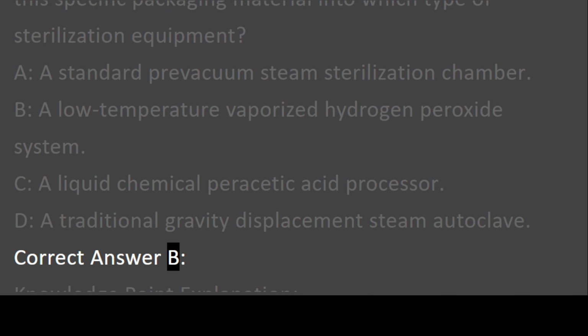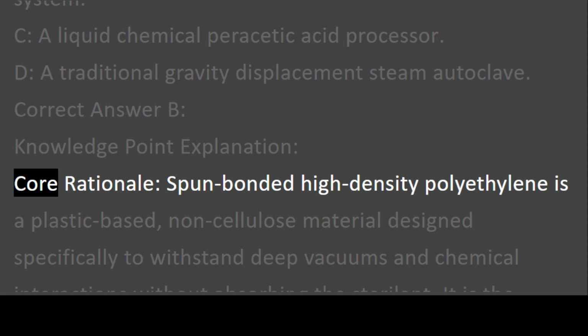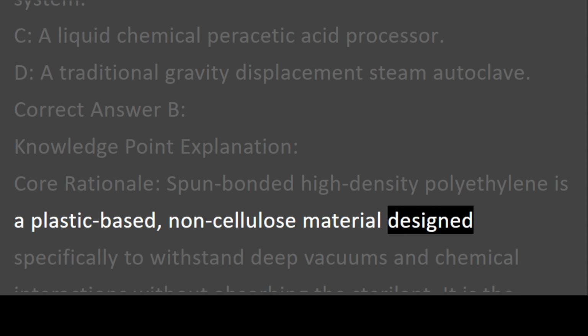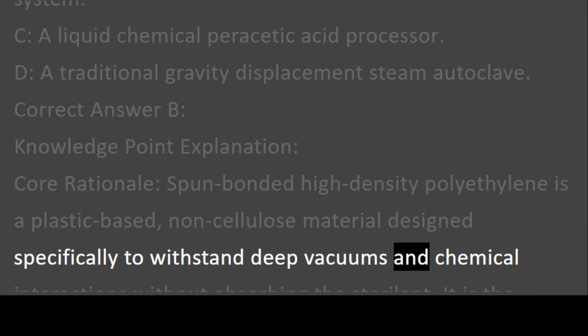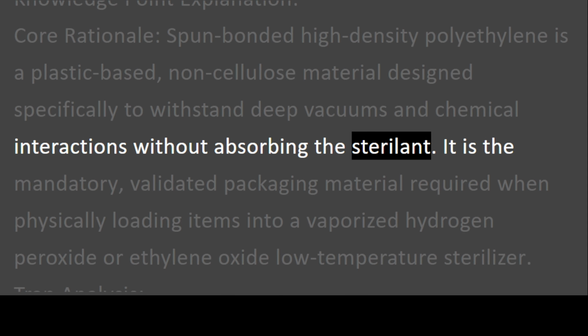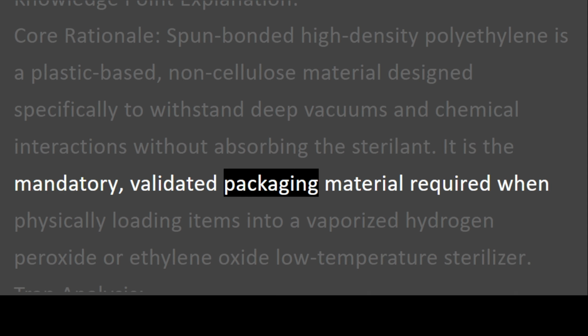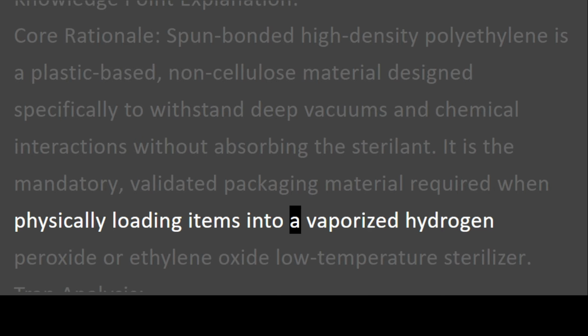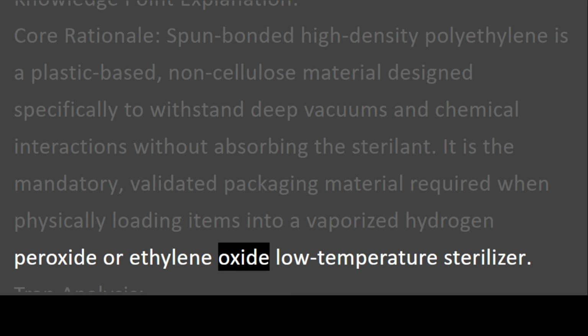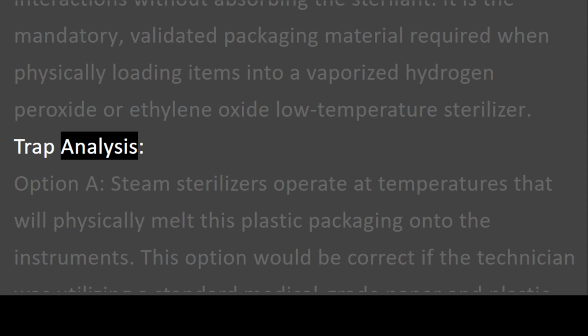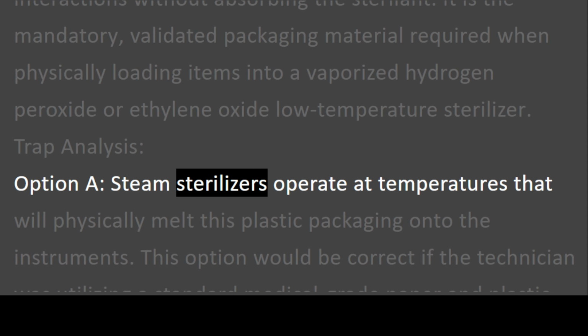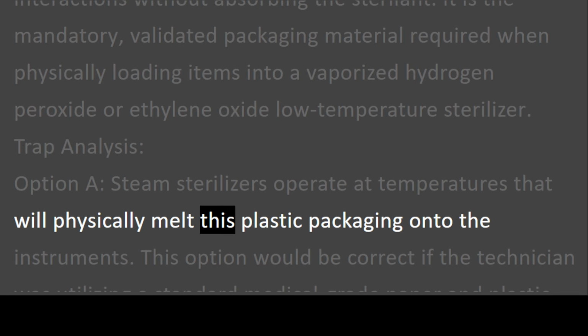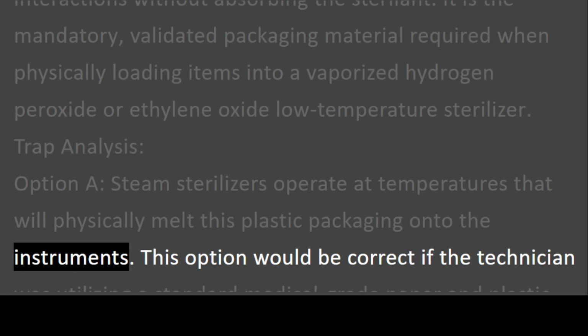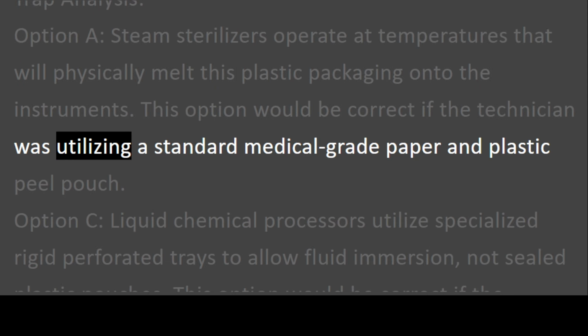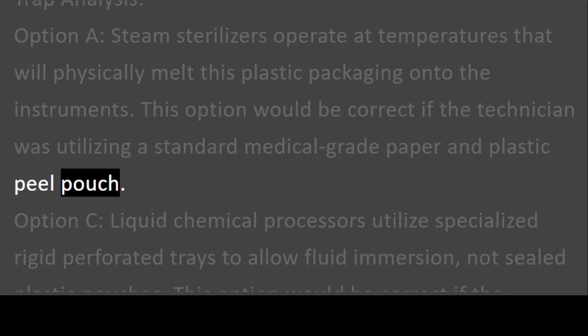Correct answer B. Knowledge point explanation. Core rationale. Spun-bonded high-density polyethylene is a plastic-based, non-cellulose material designed specifically to withstand deep vacuums and chemical interactions without absorbing the sterilant. It is the mandatory, validated packaging material required when physically loading items into a vaporized hydrogen peroxide or ethylene oxide low-temperature sterilizer. Trap analysis. Option A. Steam sterilizers operate at temperatures that will physically melt this plastic packaging onto the instruments. This option would be correct if the technician was utilizing a standard medical-grade paper and plastic peel pouch.